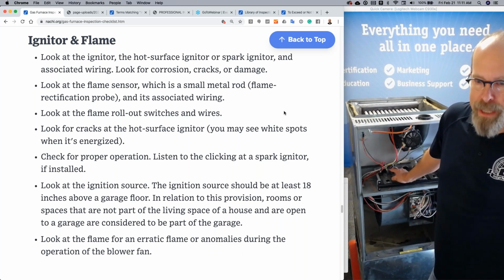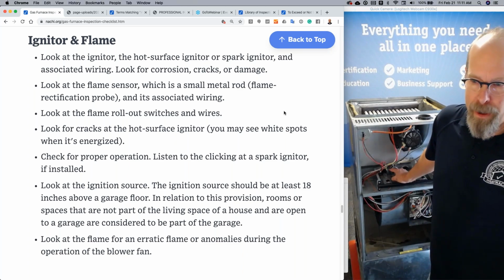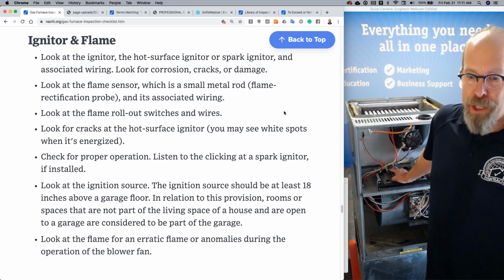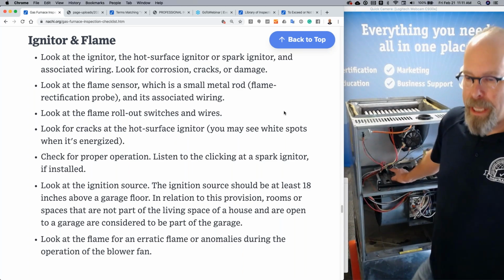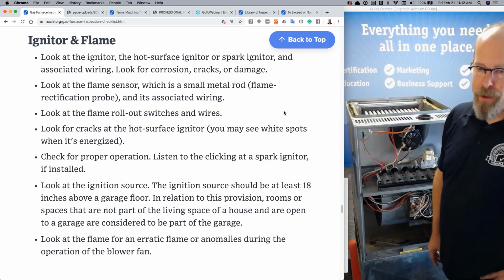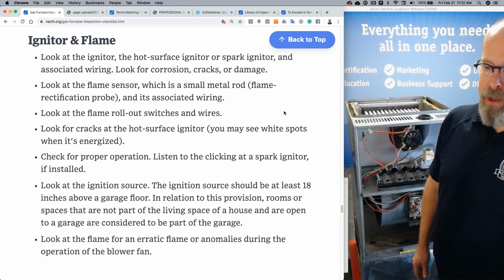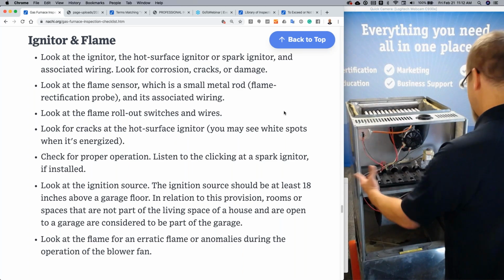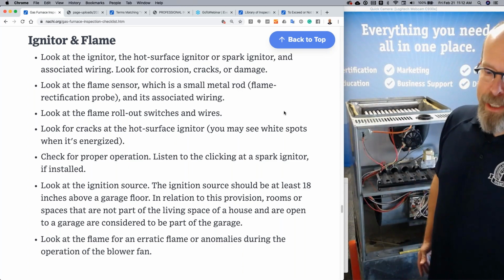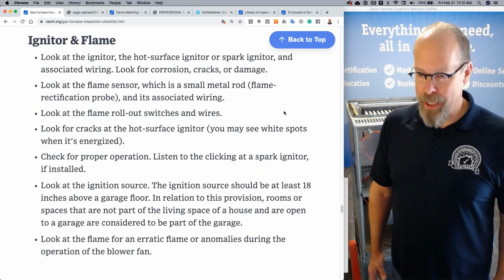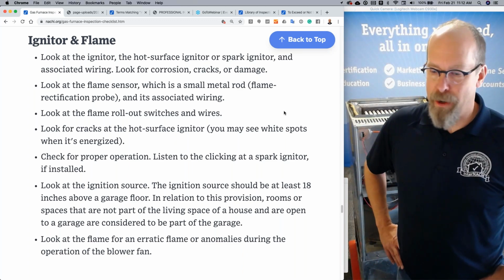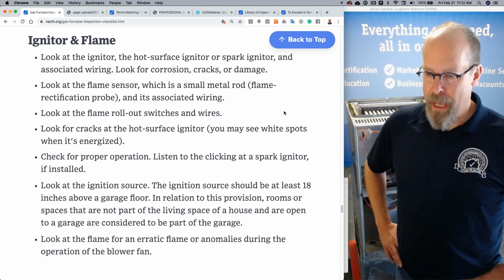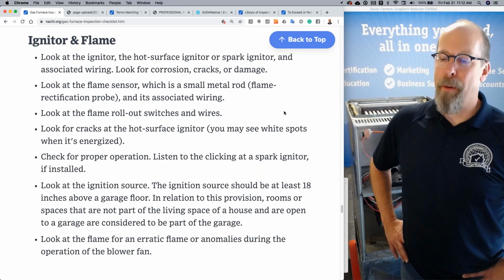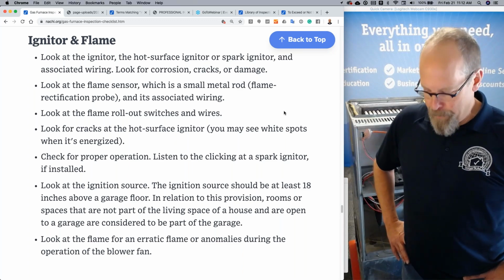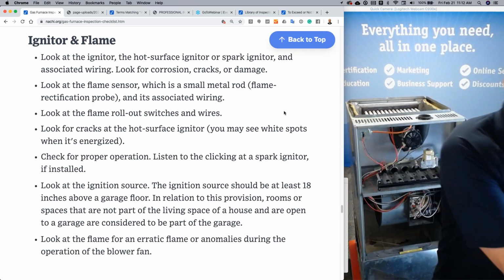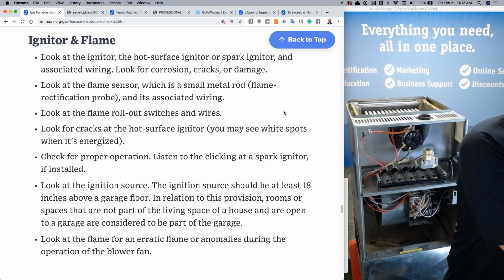Look for cracks at the hot surface igniter. You may see white spots when energized. Check for proper operation. Listen to the clicking at the spark igniter if installed. Look at the ignition source. The ignition source, which is this thing, should be at least 18 inches above a garage floor. And in relation to this provision, rooms or spaces that are not part of the living space of a house and are open to the garage are considered to be part of the garage. So that means, to me, you have to interpret code sometimes.